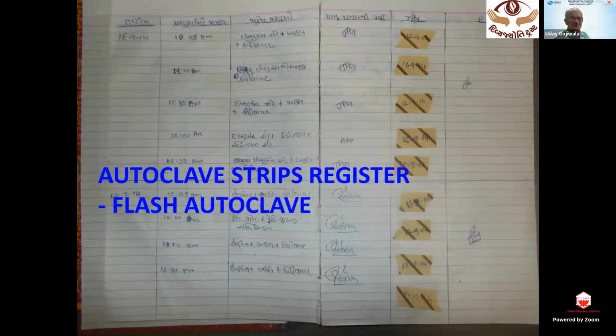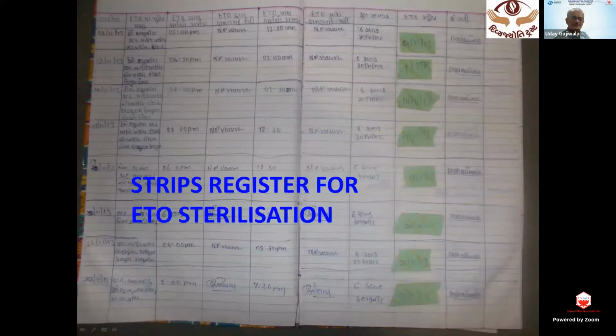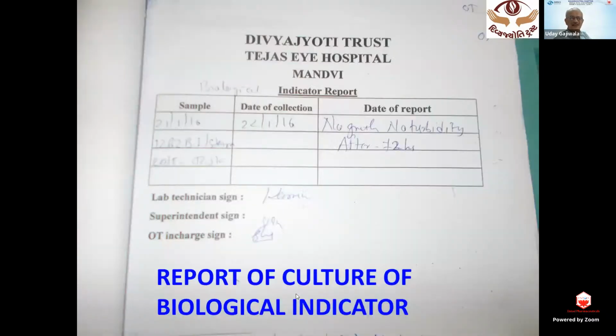Flash cycle, Dr. Purvasha also mentioned. Here also we must use a sterility indicator. Ethylene oxide gas sterilization indicator is a different color that is used for ETO sterilization. Then the biological indicator, if we use it, is sent for culture after the cycle is completed, and there should not be any growth or turbidity after 72 hours. And that is definitely telling us that sterilization had occurred for sure.